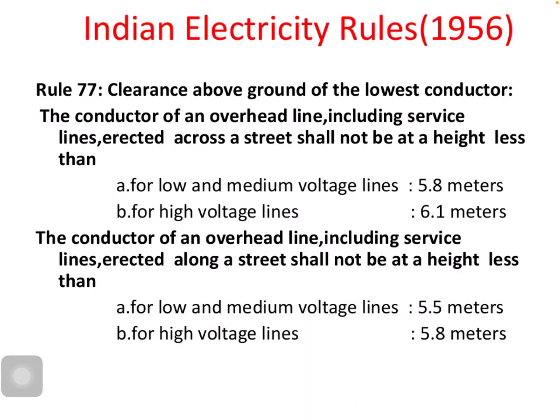The last two talk about the clearance between the conductors. The 75th rule and the 77th rule talk about the clearance above the ground, of the lowest conductor from the ground. For low and medium voltages it is 5.8 meters, and for high voltages it is 6.1 meters. For overhead lines including service lines of low and medium voltages, the minimum clearance should be 5.5 meters or 18 feet, and 5.8 meters for high voltages.